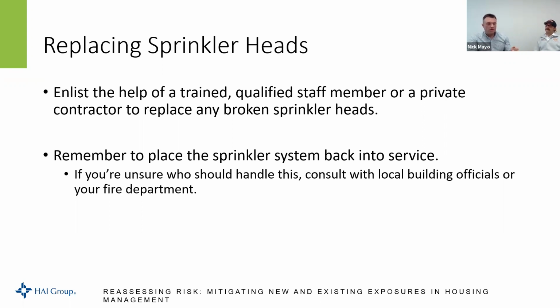We shut down the water to the sprinkler system. We replace the head, but then we forget to turn the water back on. All right, so that's an earth-shattering statistic out there: the majority of the time where something goes wrong, it's because the system was not put back in service correctly. If you're unsure of who can handle this, local building officials and your fire department can give you an answer.